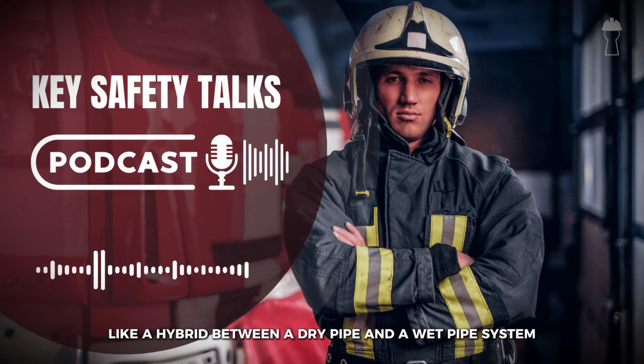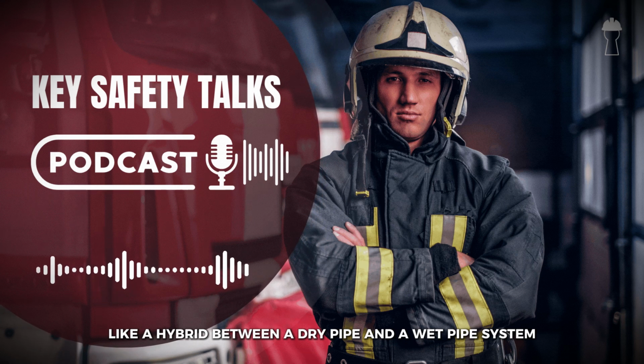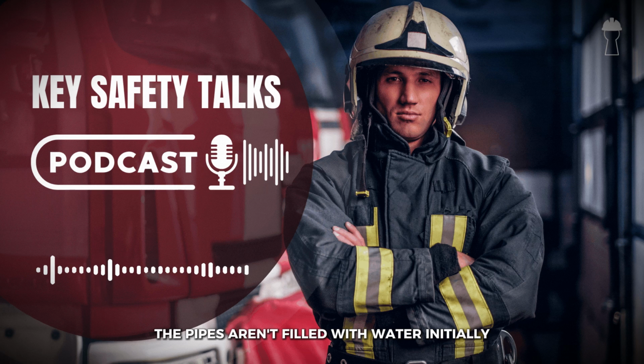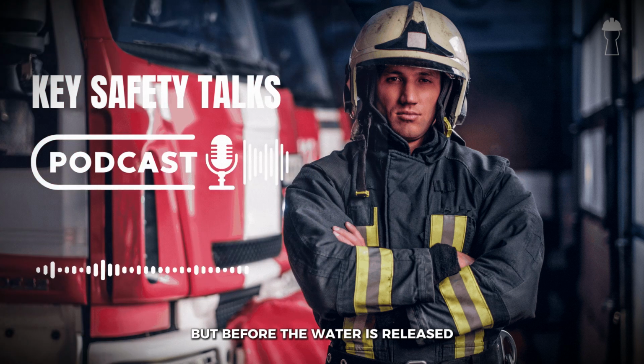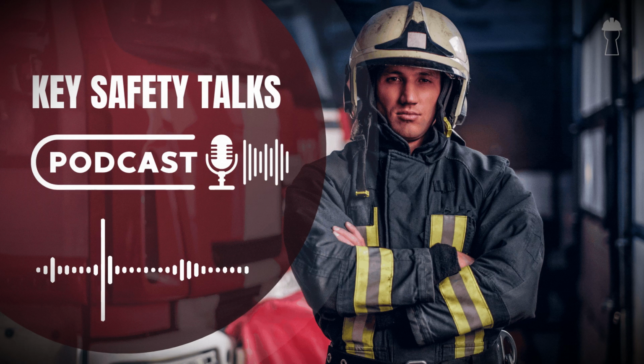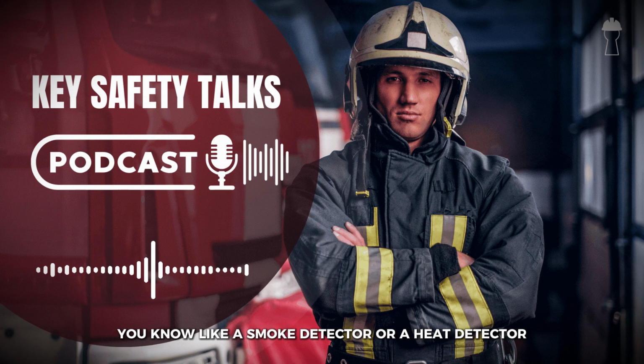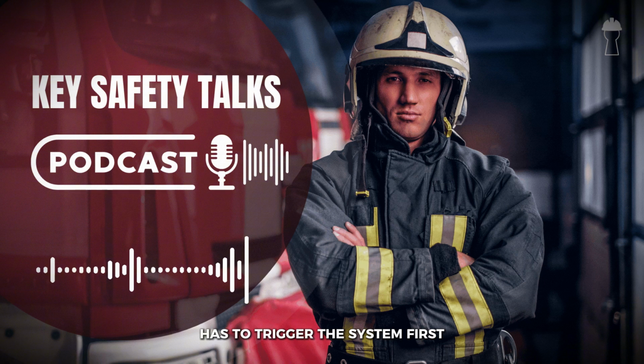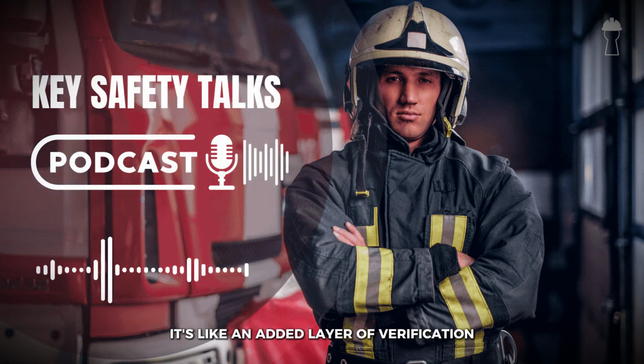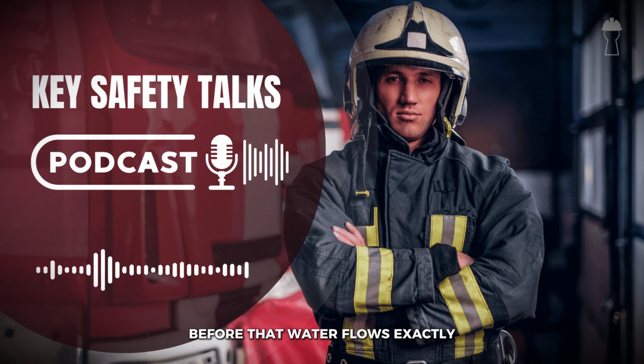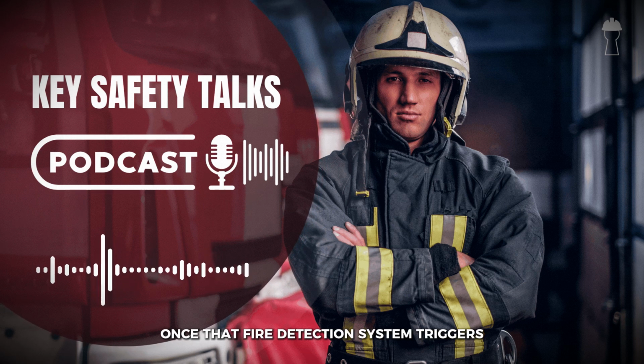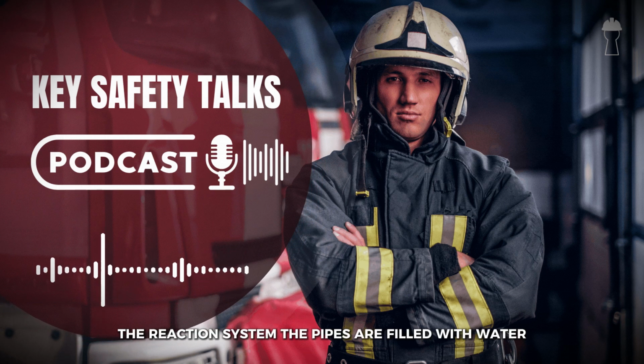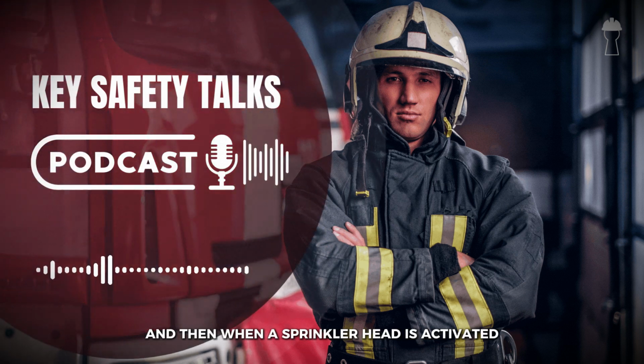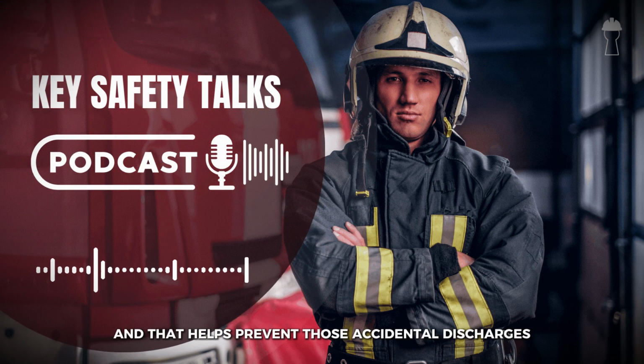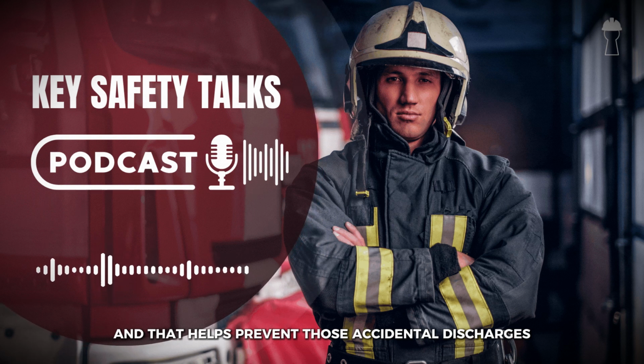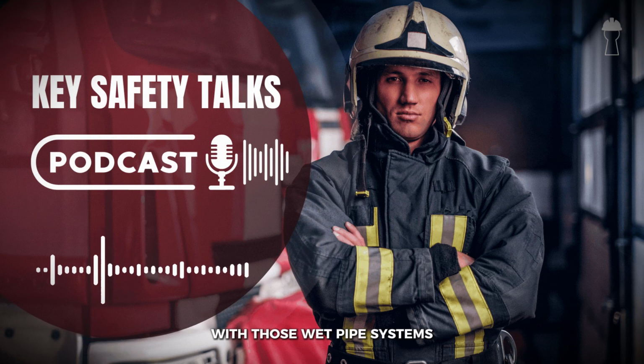They're kind of like a hybrid between a dry pipe and a wet pipe system. Like dry pipe systems, the pipes aren't filled with water initially, but before the water is released, there's an extra step. Typically, a fire detection system, like a smoke detector or a heat detector, has to trigger the system first. Okay, so it's like an added layer of verification before that water flows. Exactly. Once that fire detection system triggers the pre-action system, the pipes are filled with water, and then when a sprinkler head is activated, the water is released, and that helps prevent those accidental discharges, which can sometimes be a concern with those wet pipe systems.